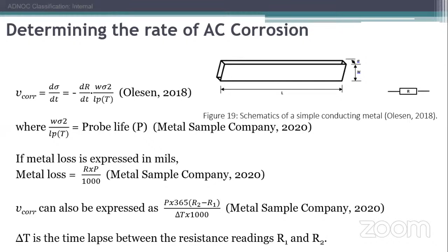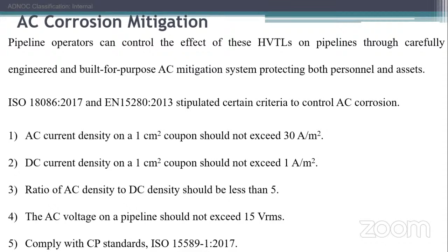This is a formula for calculating the rate at which AC corrosion is progressing, so we can protect our pipeline from this form of corrosion. If we ensure AC corrosion does not exceed 30, our line is safe. If the DC also does not exceed 1, our line is safe. These measures just guide us.